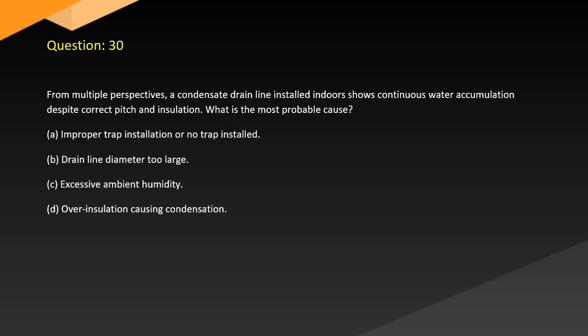Question 30. From multiple perspectives, a condensate drain line installed indoors shows continuous water accumulation despite correct pitch and insulation. What is the most probable cause? A. Improper trap installation or no trap installed. B. Drain line diameter too large. C. Excessive ambient humidity. D. Over-insulation causing condensation.